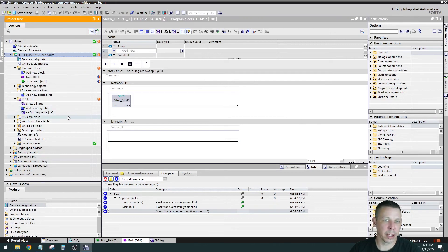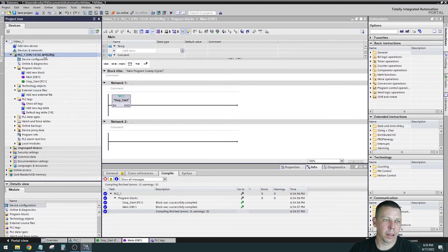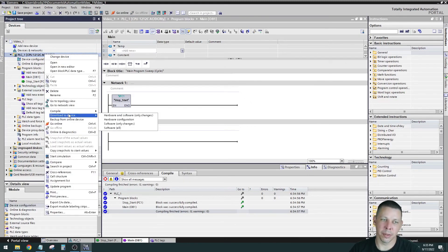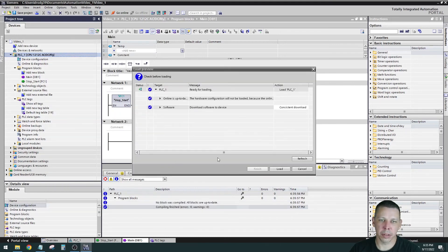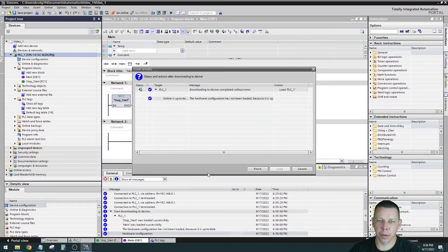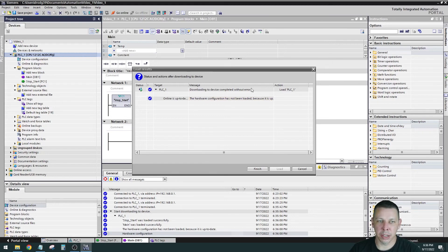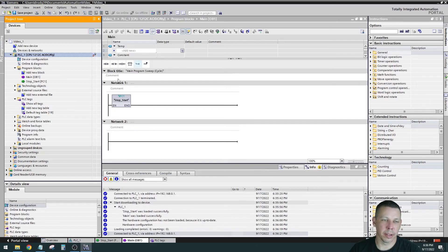I compiled it but didn't download it, so I'll go back offline. You have to compile hardware, compile software, and then download to the device. So I compiled but never sent it into the processor. Now go to Download to Device — hardware and software only, changes only. It says the hardware configuration has not been loaded because it's up to date — the hardware didn't change, same processor, same firmware. It did download the software though.